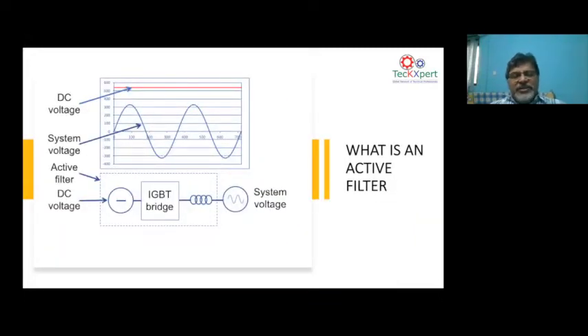Now, an active filter is in principle just like a VFD, because a VFD also has rectifiers and IGBTs. So here also it has the same thing, but in a different topology. An active filter fundamentally has an IGBT drive, and we call it a voltage source inverter. The fundamental of a voltage source inverter is that it has a DC source, that is a battery, and the power electronics converts the DC voltage to the required AC voltages. In an active filter, it is trying to create harmonic currents at multiple harmonic frequencies, so the IGBT bridge is doing that function. Go to the next slide.